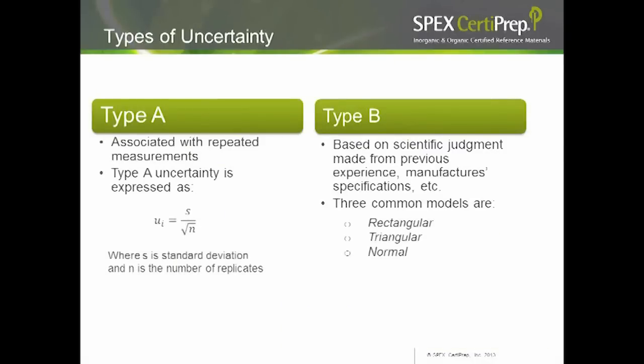To determine your uncertainty, you first determine what you wish to measure, outline the process you are conducting, identify all sources of uncertainty, estimate the uncertainty from each source, and finally combine and expand all your uncertainties. Once you determine your sources of uncertainty, you must decide what type it is. Type A uncertainty is associated with a number of measurements or a standard deviation of a mean. Type B uncertainties are based on scientific judgment and experience. There are three common models of uncertainty: rectangular, triangular, and normal.